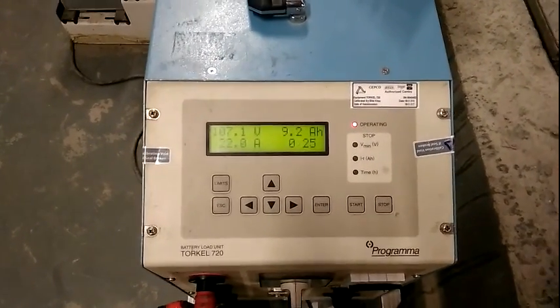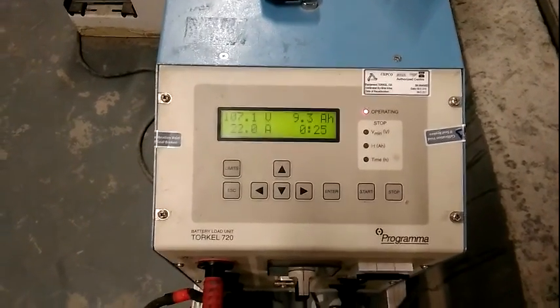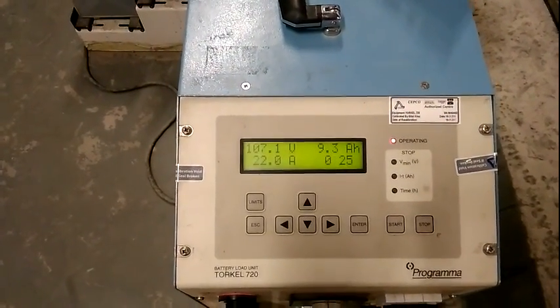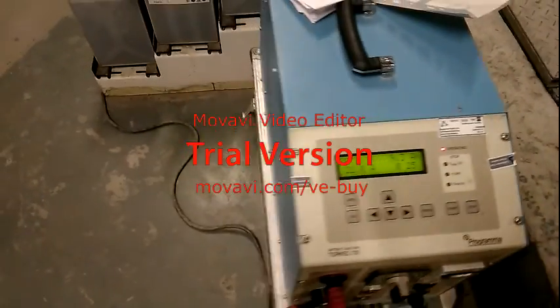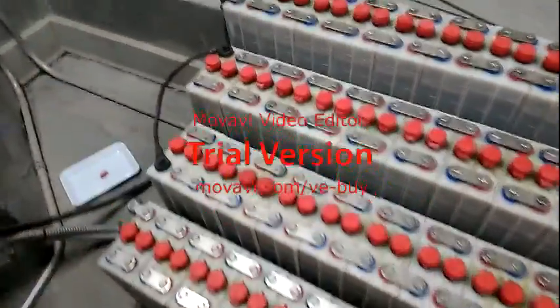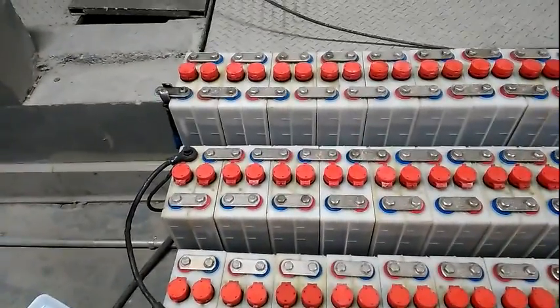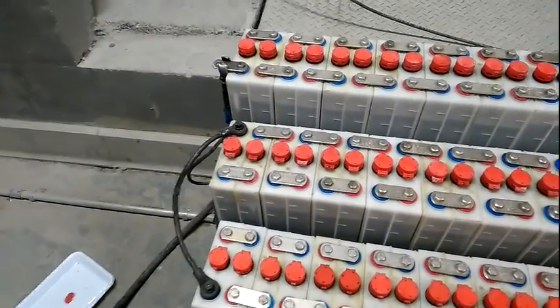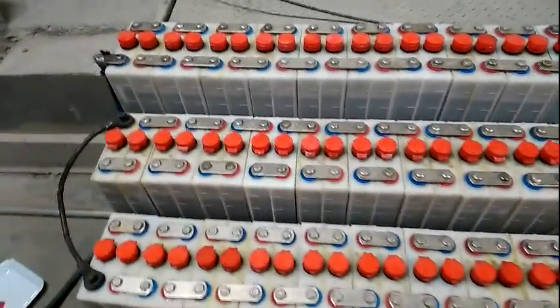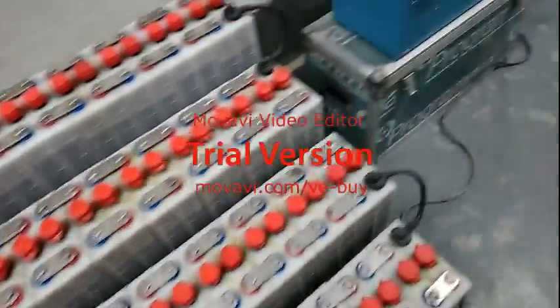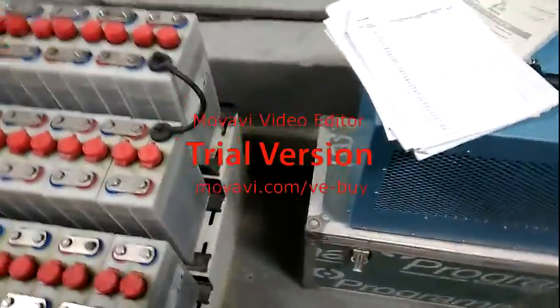Now 25 minutes have gone and the voltage decreases each hour. Now the voltage is 107. This test is totally 5 hours. After 5 hours are finished, the voltage will have decreased each hour and the value of current will have increased each hour up to 110 amps. After finishing this 5-hour test, this voltage will become less than 100.